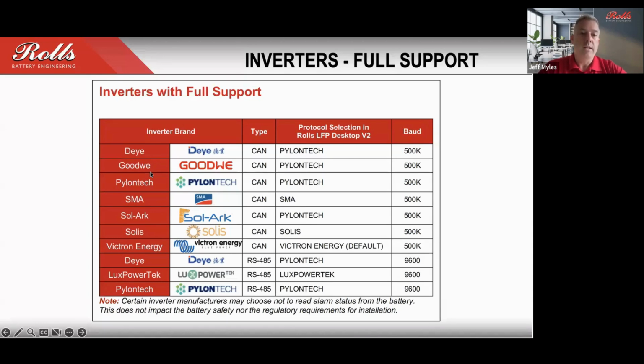And so what we've done, going through the testing process, is identify, based on the protocol that has been set, whether or not that particular unit shares that information with the customers through the inverter. So this particular list will provide you the protocol that's associated with that particular brand of inverter. And that protocol would be selected whether you assign it through the LFP Connect app or through the PC software. You're essentially going to pick that particular protocol that's listed in the table. And once that's assigned to the battery, it will be compatible to connect and to share that status information with the inverter.